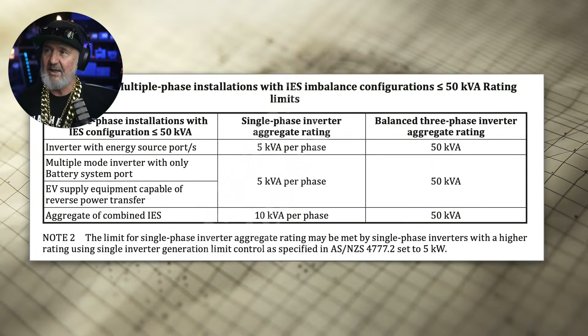The vehicle itself, in Australia and New Zealand, to be able to do this, would have to be 4777 Part 2 approved. So vehicle manufacturers would have to go and get their inverters 4777 Part 2 approved. Probably not going to happen. We'll come on to EVSEs in a minute, explaining the different modes that you can charge or connect them. And where you've got an aggregate of multiple inverters, it's up to 10 kVA per phase. So if you've got two 5 kVA inverters together, that's a maximum of 10 kVA. Now, of course, the caveat is any of this can be overridden by lines companies and DNSPs. So these are just guidelines in the standard.